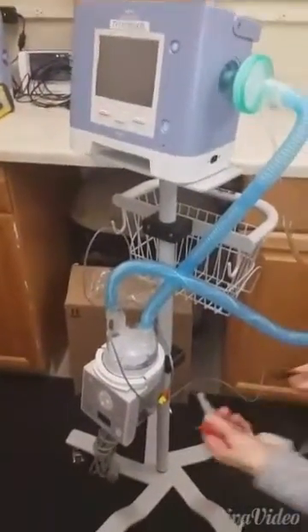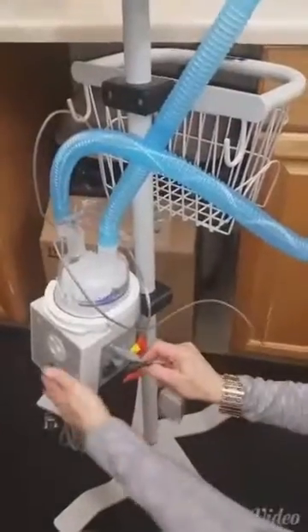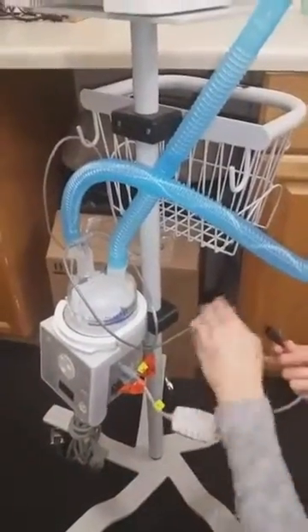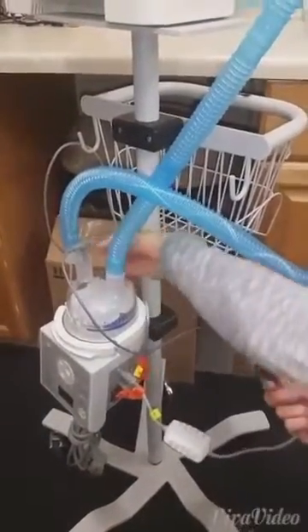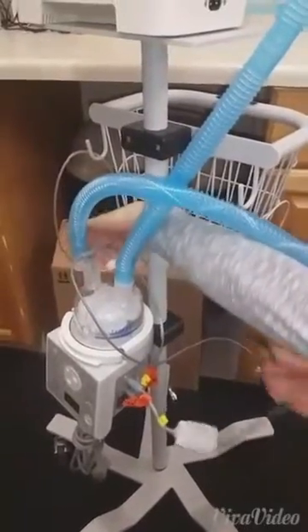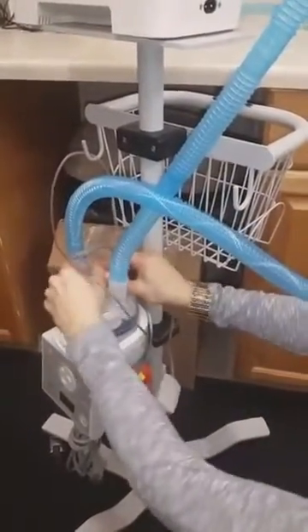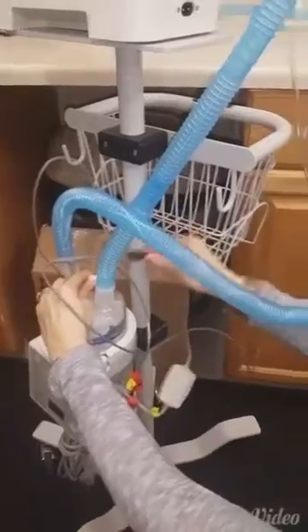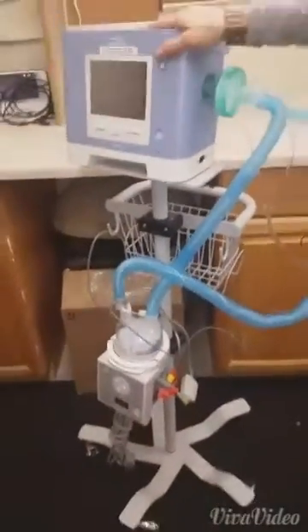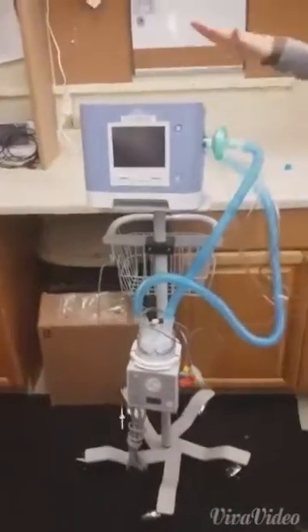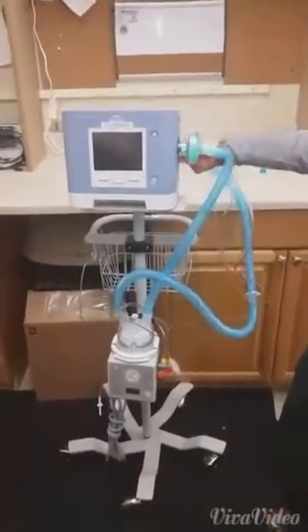Then you'll take your heater wire. You'll plug it into the heater wire spot. There's only one place for it to go. Then you'll take the heater wire connector that's on the tubing, and you'll plug that in here. And that's how you set up a heated circuit on a Trilogy 100 with an active circuit.